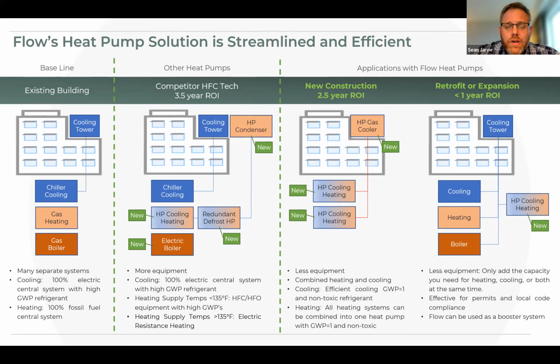What a lot of people are doing on these heat pumps, because we have limits on the maximum temperature that we can do, and the way we handle defrost in those systems, because of that reversing valve, we have to always size a redundant module to keep heating on when we go into cooling, because they flip the thing into cooling mode and it's cooling down our inside space, where we don't want to do that. So we always have to design a redundant defrost module. Now there's a lot of new equipment and it gets really complicated.